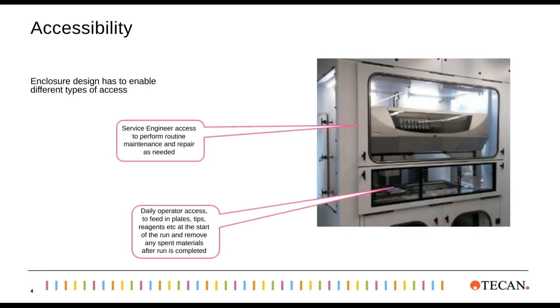You've also got to consider the accessibility. Two types of accessibility are needed. The daily operator access, where you're going to be loading in plates, tips, reagents, etc., and then physically taking those out at the end of a run. You've got to make sure that the operators can reasonably access all parts of the instrument and the work deck. Oftentimes you'll have, and you can see it in the photo here at the bottom, at the back, plate hotels, hotels for tips, etc. Those have got to be realistically accessible by the lab staff.